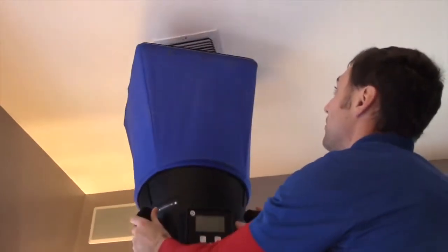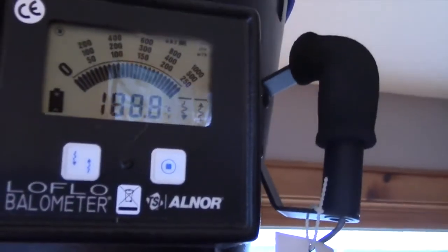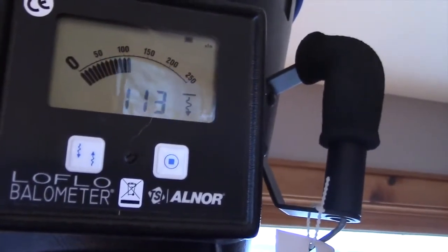So measuring airflow is really important, and there are some times where the airflow is not matching up, it's not balanced throughout the house. And what that means is that there's more airflow going other places in the house that don't need as much airflow, and less airflow going to the places where more is needed. And in that case, dampers should be adjusted in order to balance the house so that everything cools down or heats up at the same time. You don't want rooms that are too stuffy or rooms that are too cold. So that's what's important about that. So there are times where systems need to be balanced with dampers to ensure that every room is balanced appropriately.